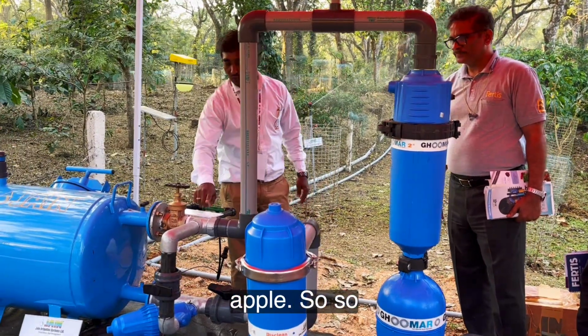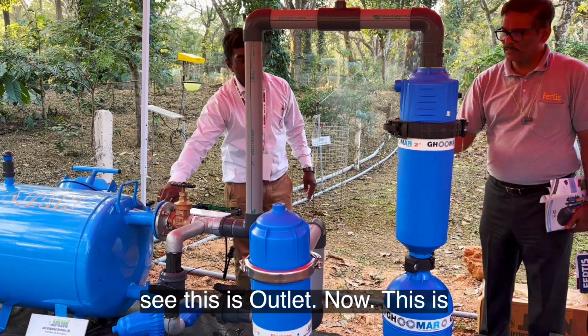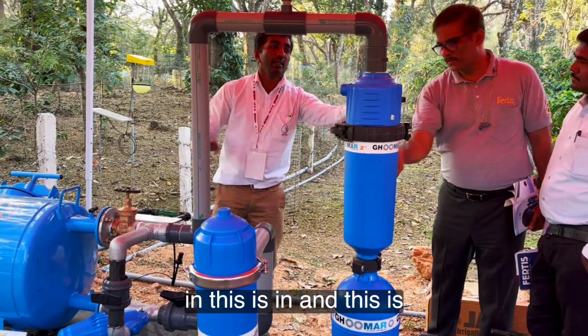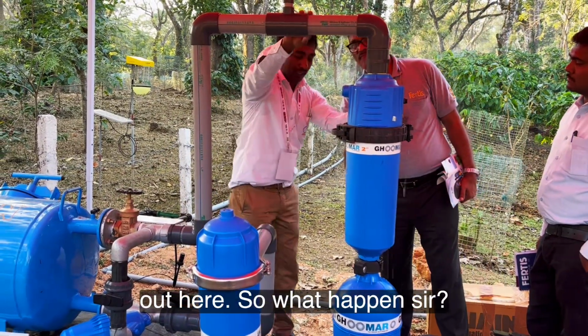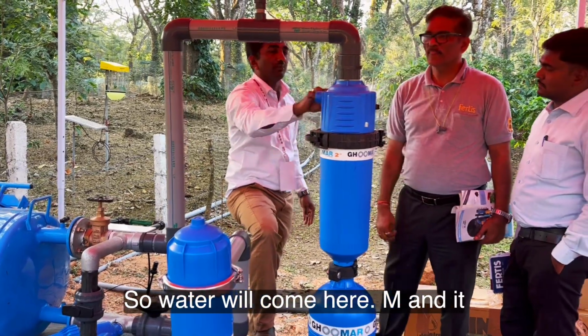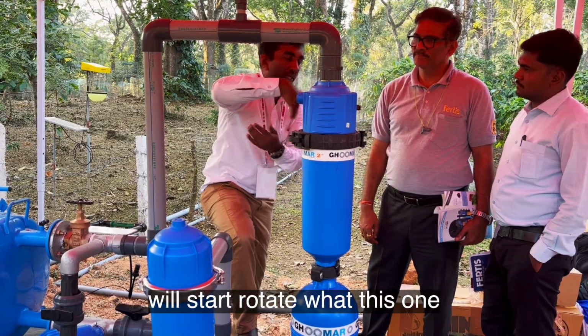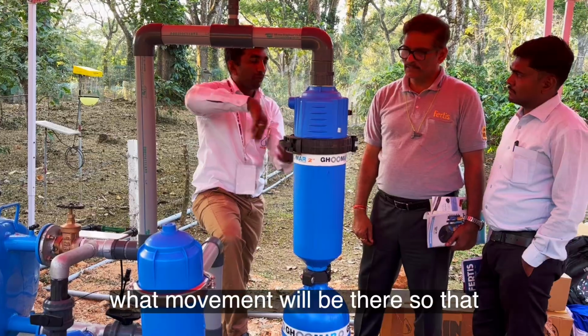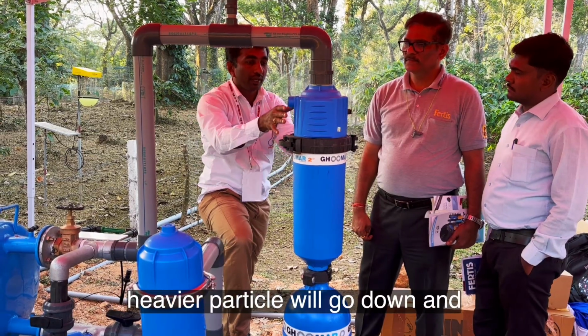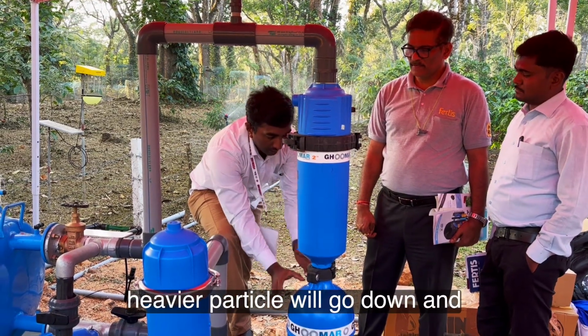See, this is the outlet. This is the inlet of the filter, and this is the outlet. So what happens, sir? Water will come here and it will start to rotate. A vortex movement will be there, so that the heavier particles will go down and collect in this chamber.